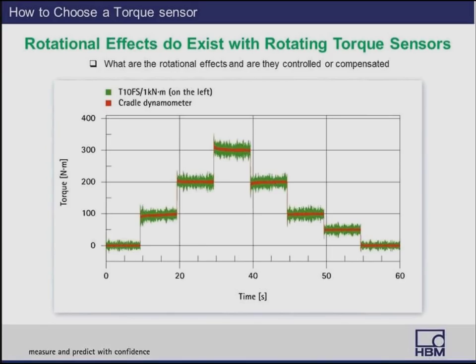Rotational effects do exist with rotating torque sensors. Unfortunately, they generally aren't listed on the data sheet because they vary depending on RPM and can vary from application to application, making them very hard to quantify. However, they exist on every torque sensor, and some companies compensate for rotational effects while others do not. It is important to ask your vendor what the rotational effects are and whether they are compensated for.